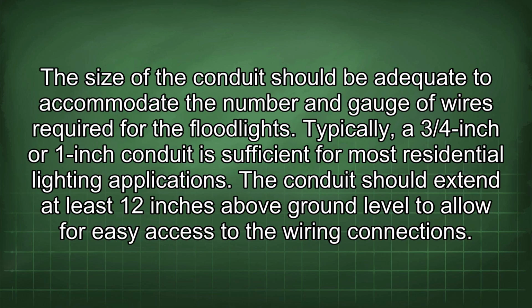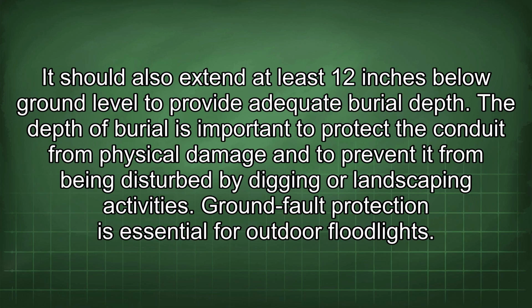The size of the conduit should be adequate to accommodate the number and gauge of wires required for the floodlights. Typically, a 3/4 inch or 1 inch conduit is sufficient for most residential lighting applications. The conduit should extend at least 12 inches above ground level to allow for easy access to the wiring connections. It should also extend at least 12 inches below ground level to provide adequate burial depth.